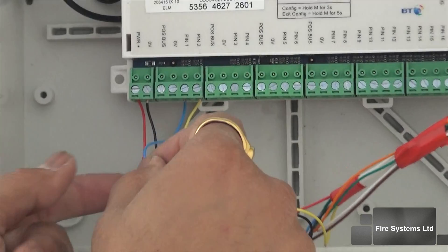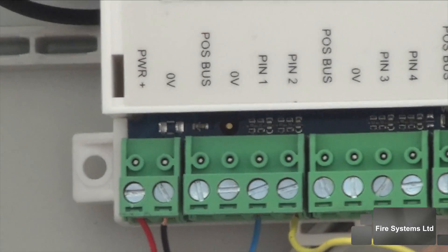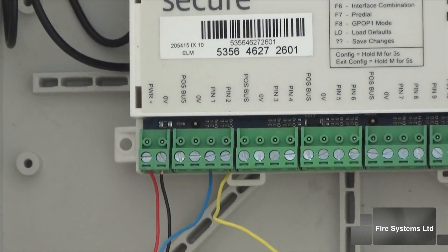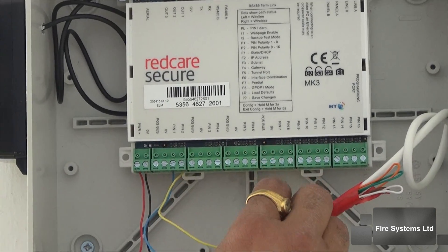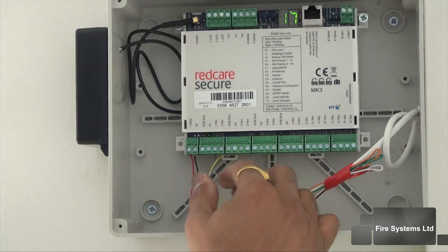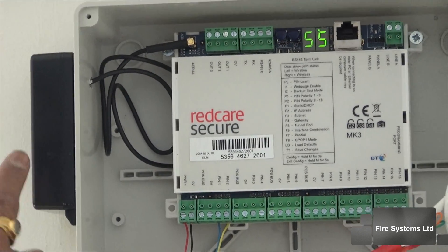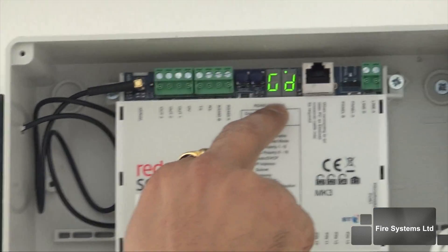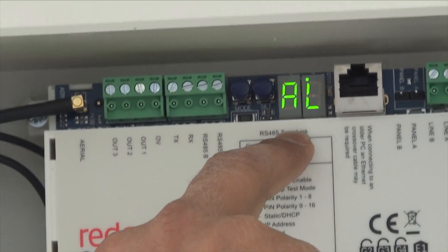The wiring from the fire alarm fire and fault relays are connected to the redcare secure unit as shown. Fire is the blue wire on pin 1 and the fault is the yellow on pin 2. The red and black wires are the power to the unit. The black box to the left is the antenna, which is used to transmit the alarm signals using the GSM network. The digital display provides the GSM signal strength and alarm signal information.